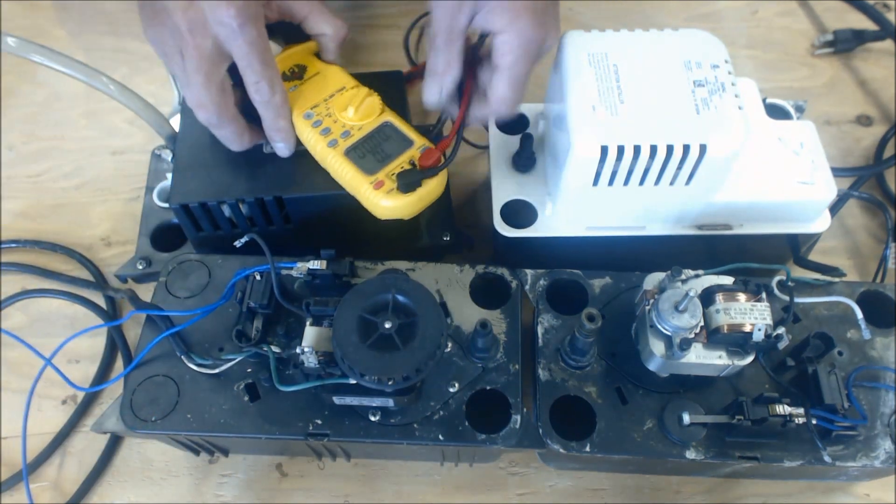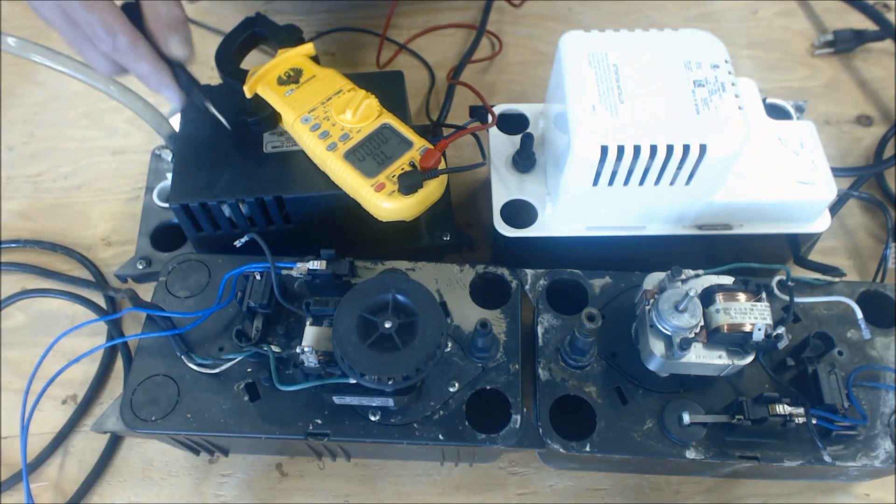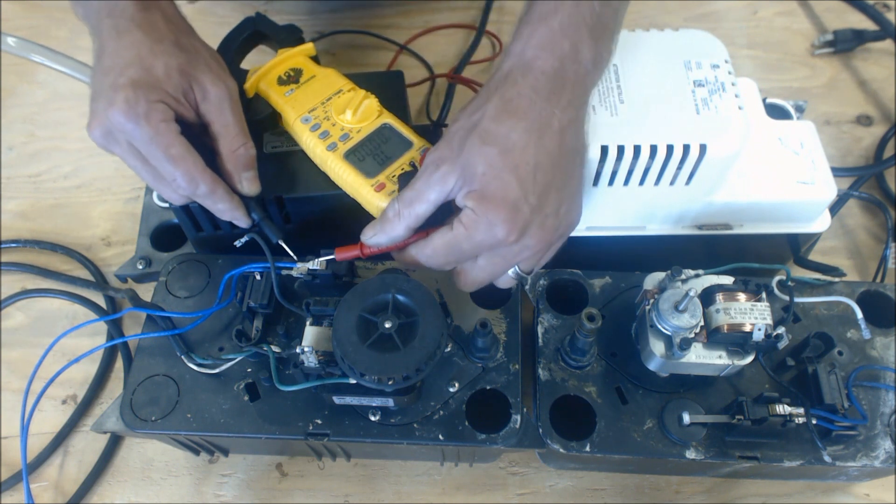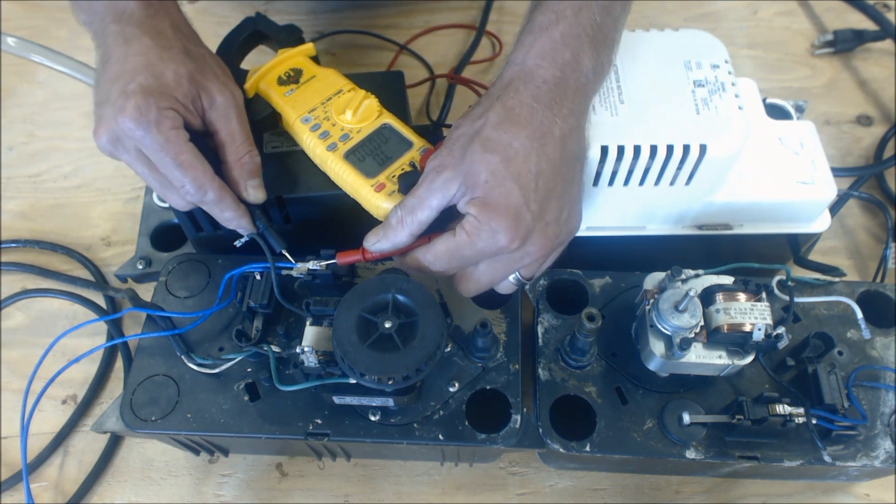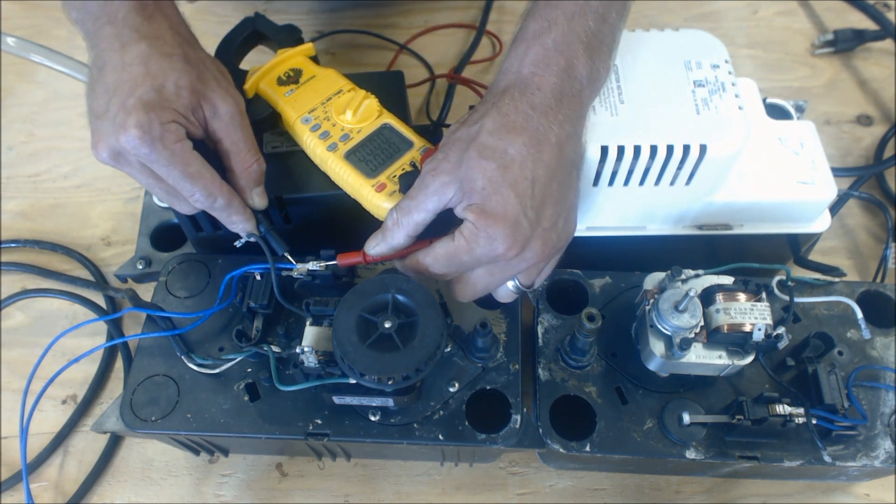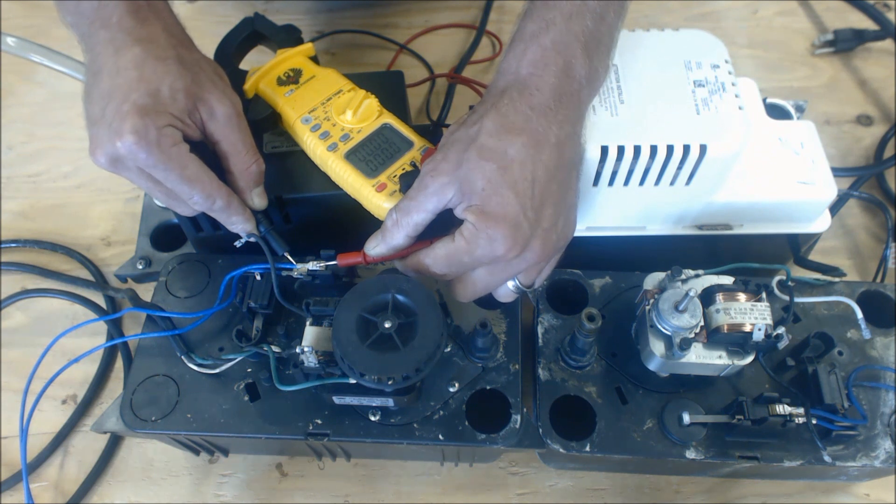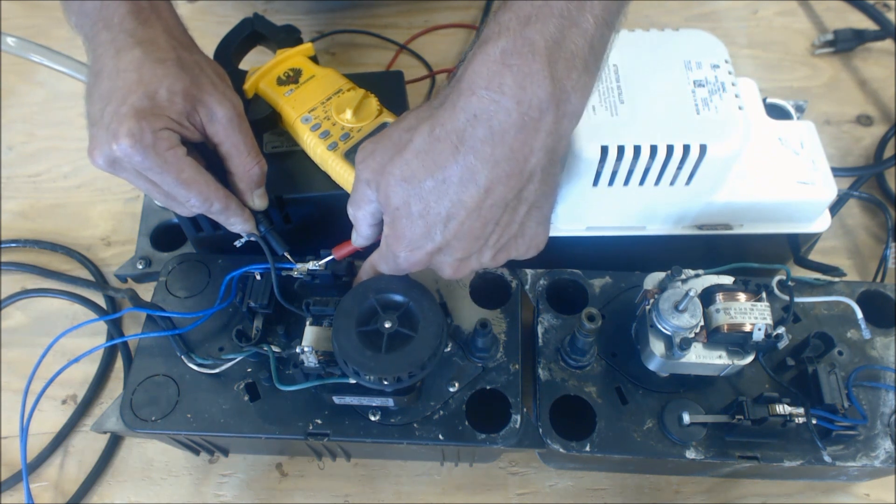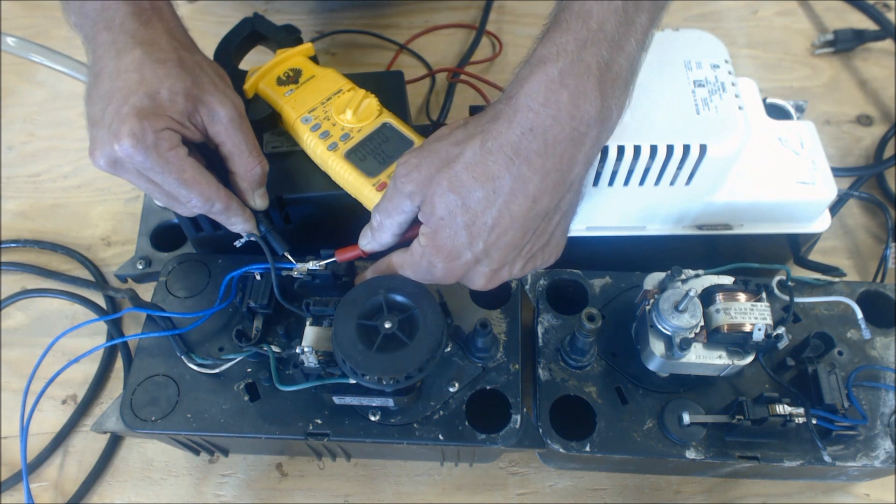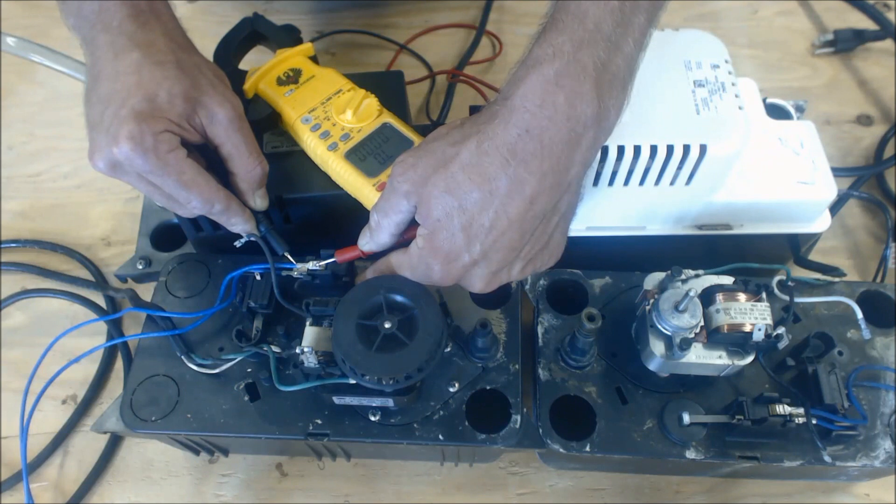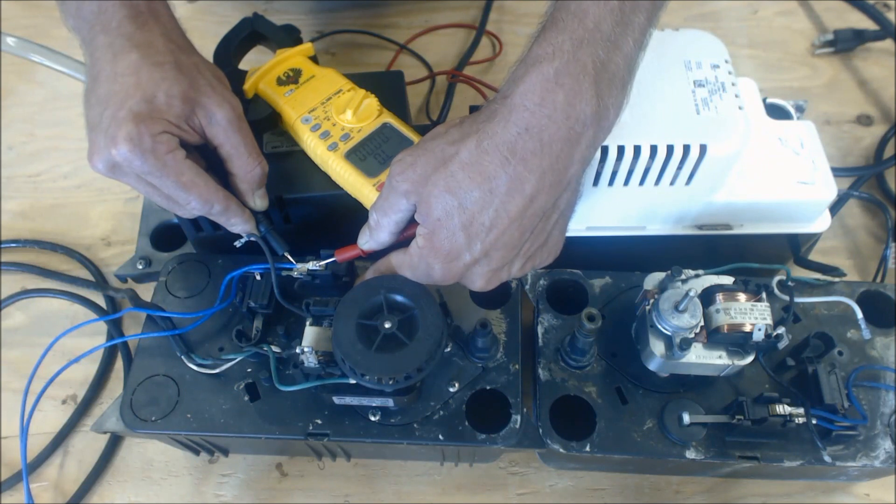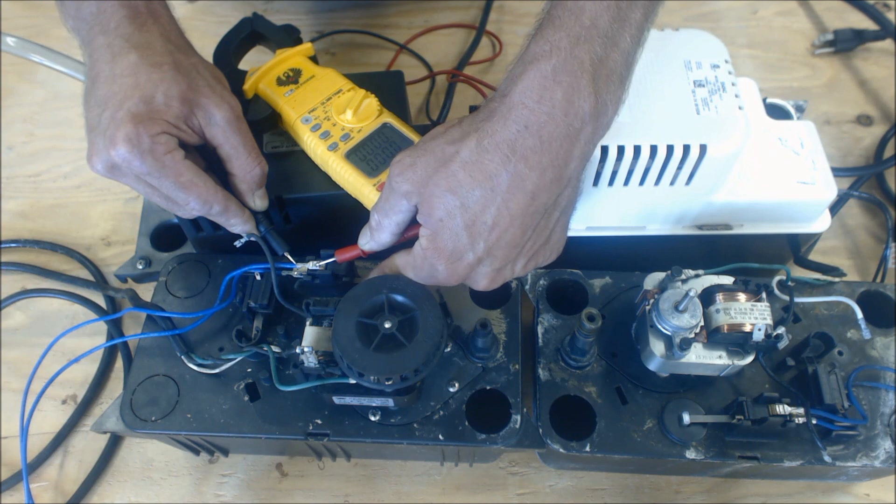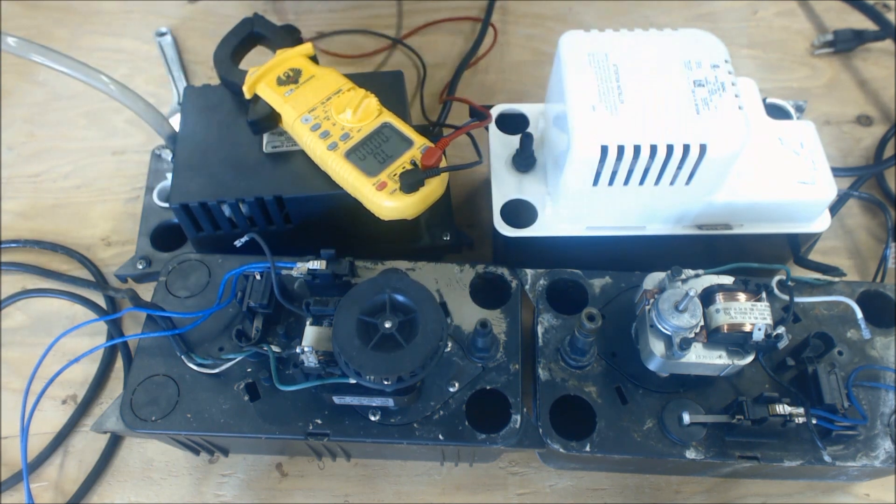So it should read 0.0 ohms of resistance if the micro switch is correct. So that is working well. Now we're going to lift the switch and it opened up the wiring. Let it back down, it reads 0.0 ohms of resistance again.